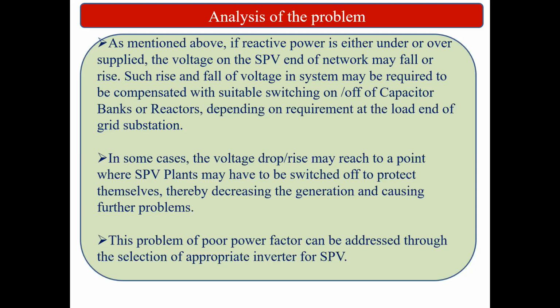Now what is the solution for that? The solution for this is to size the optimum capacity of the capacitor banks, which can be installed in this system, so that our power factor issue is getting cleared. Okay, so this is one of the power factor related problems related to the solar PV system and the mitigation issues as well. So the final year student can take this as a case study with the actual loads and with actual facts and figures. They can size the optimum capacitor bank for a client.